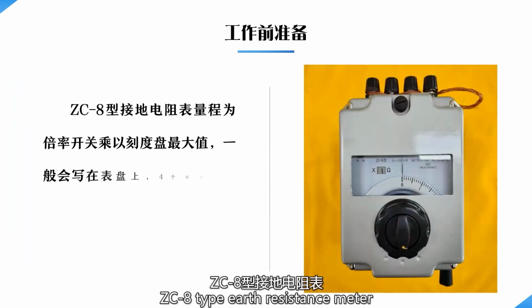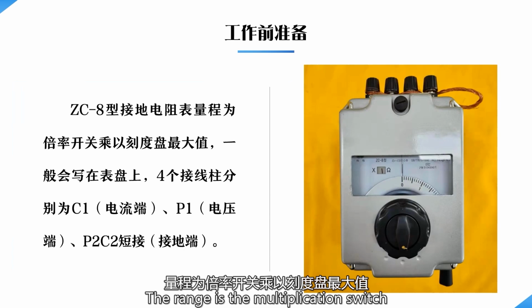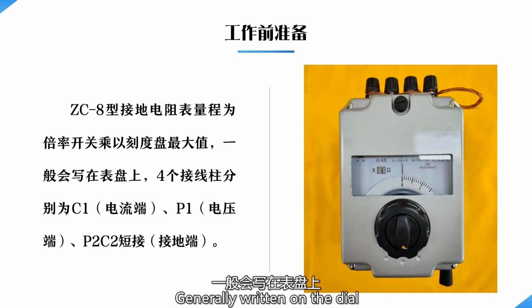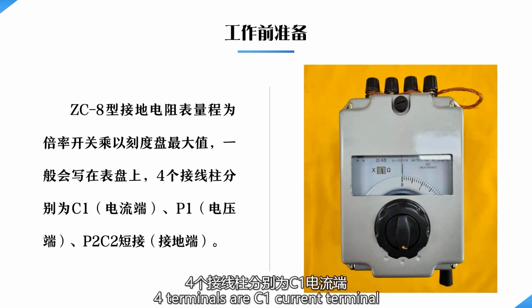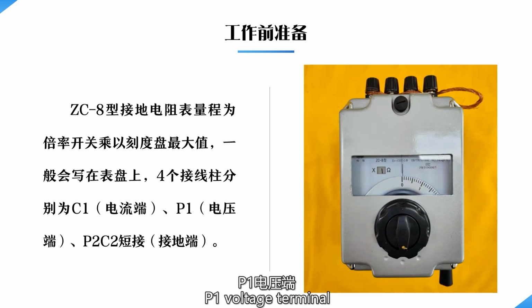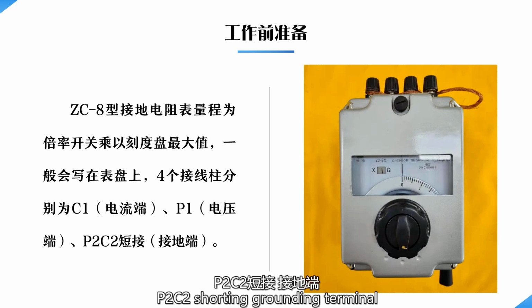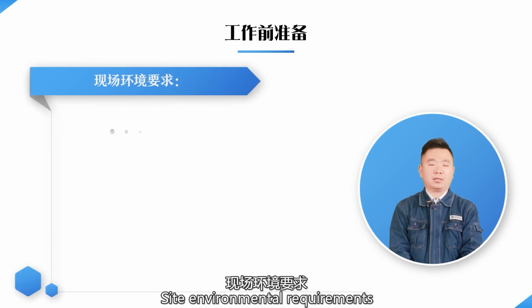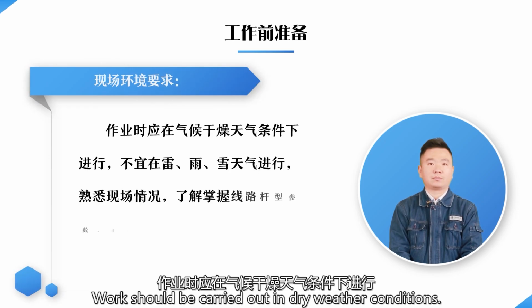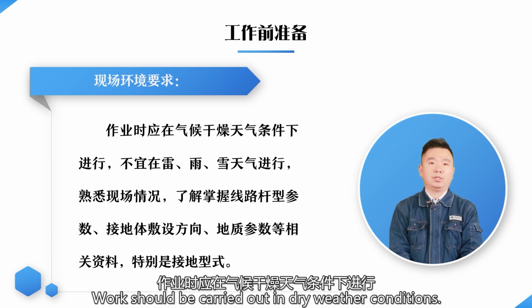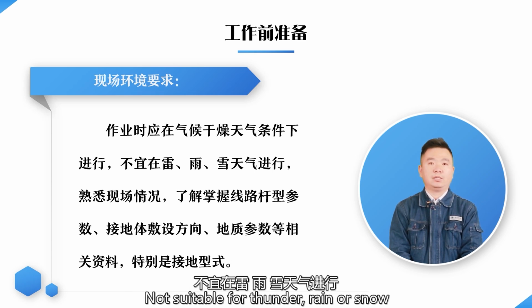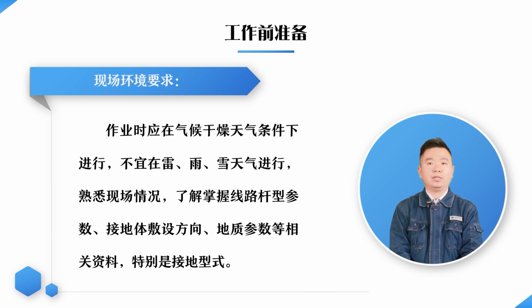ZC8 type earth resistance meter. The range is the multiplication switch multiplied by the maximum value of the dial, generally written on the dial. The four terminals are the C1 current terminal, the P1 voltage terminal, and the P2 and C2 shorted grounding terminal. Site environmental requirements: work should be carried out in dry weather conditions, not in thunder, rain, or snow.